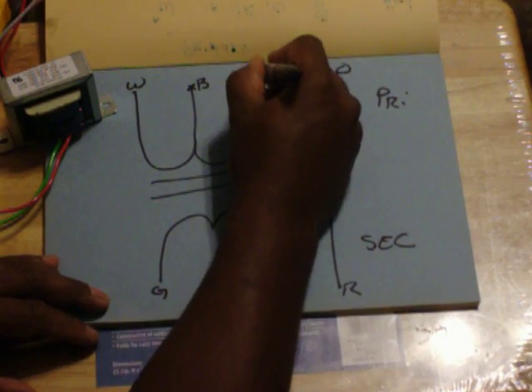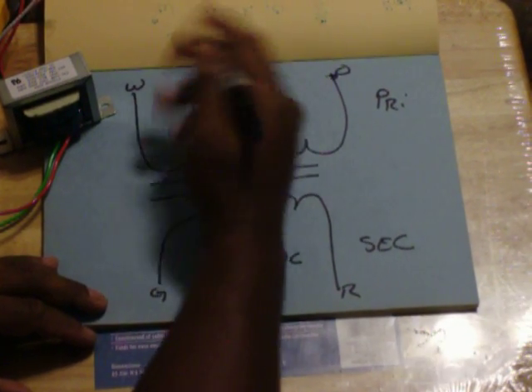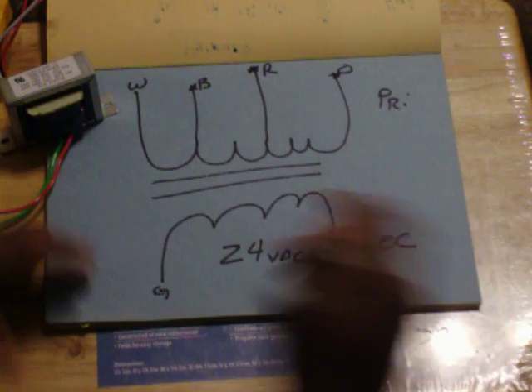So no matter what, you're going to use white. Whatever you don't use, you cap them off. Do not hook them together. Cap them off. If you hook them together, you're going to short it out. But no matter what voltage you hook up, you're always going to come out with 24 volts.